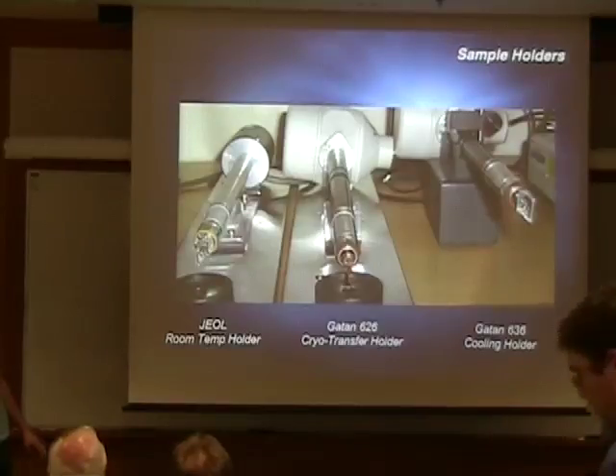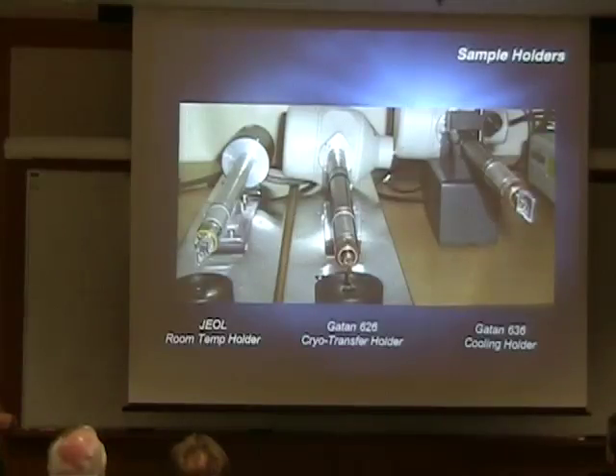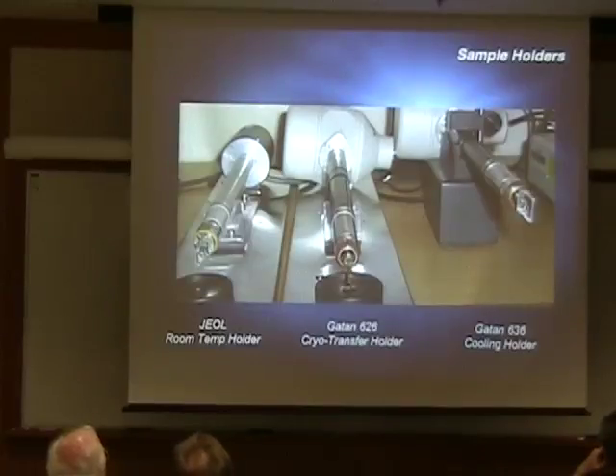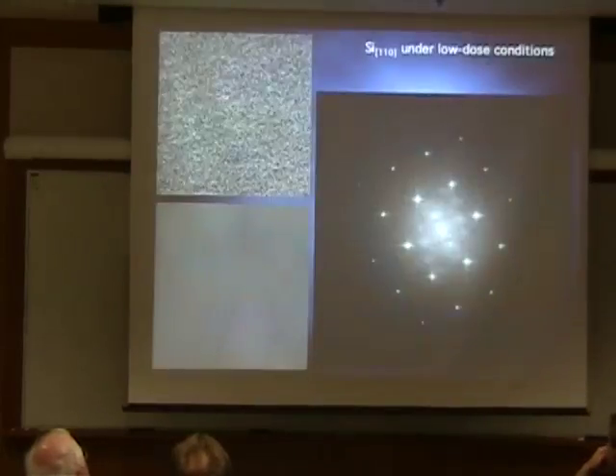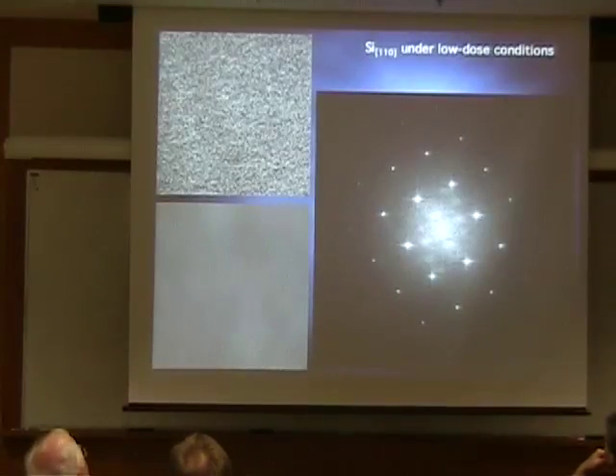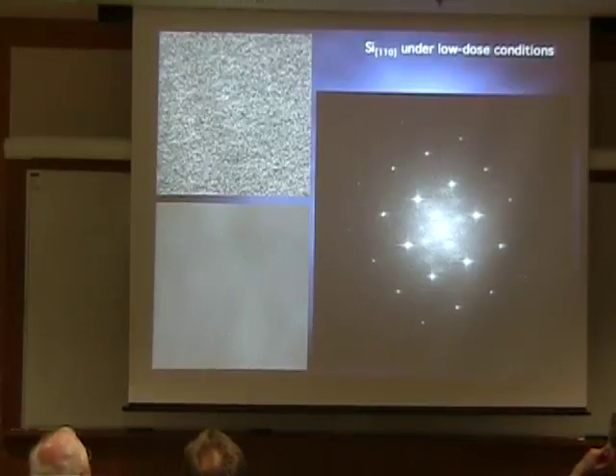The first issue: the 2200FS microscope has a URP pole piece, so there is no standard cryo-transfer holder that can be placed inside the microscope. The 626 holder, which is the typical cryo-transfer holder, is about three times thicker than either the room temperature holder or the Gatan 636 cooling holder. So we wound up using the Gatan 636 cryo-holder, which we have to load at room temperature and then cool down once inside the microscope.